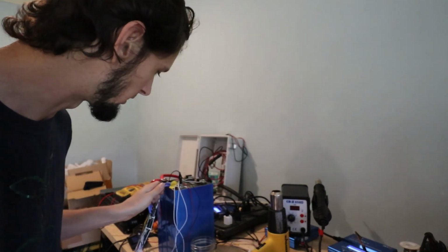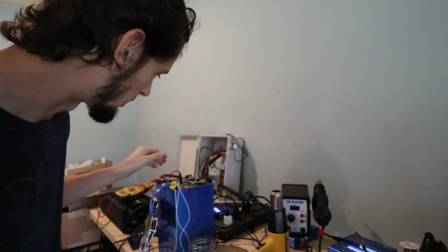The 10 gauge wires do get pretty warm, but it was like 100, 105 degrees on the thermal camera, so that wasn't too bad. I consider that acceptable. Wasn't quite running it at the full rated amperage.